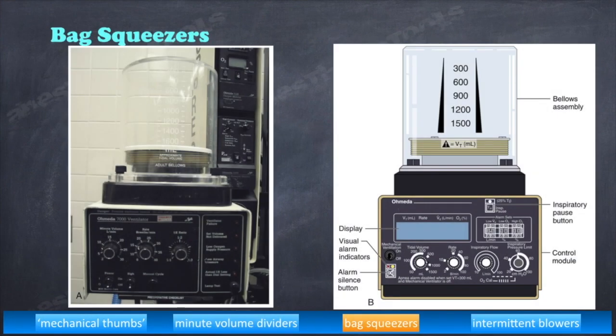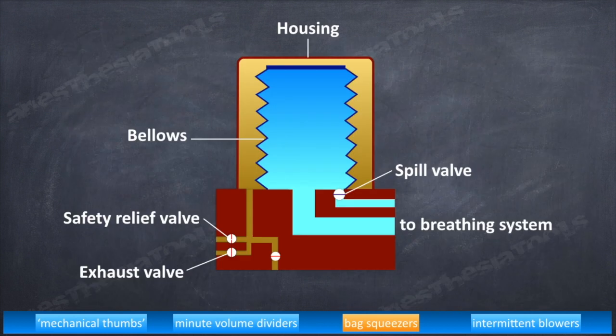Now type three: bag squeezers. This one relieves the anesthetist of having to squeeze the reservoir bag and, apart from freeing him or her to do other things, offers the advantages of producing more regular ventilation with controllable tidal volume and pressure. Here, bag and bottle bellows design, ascending bellows variety is shown. Please note that the bellows displayed in the images are deflated.